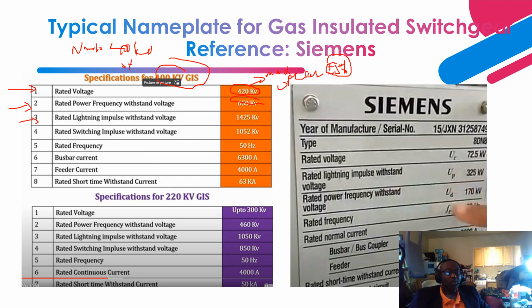Next is lightning impulse withstand voltage. If you have a GIS that is located in close proximity to a lightning strike, those lightning impulses have a very steep front, then tail off to 50%. To achieve 90%, it is a very steep front, right? So this is how much the insulation has been built to withstand, because lightning impulse delivers a very high overvoltage. The GIS and its insulation system have been built to withstand that and protect the internal components.